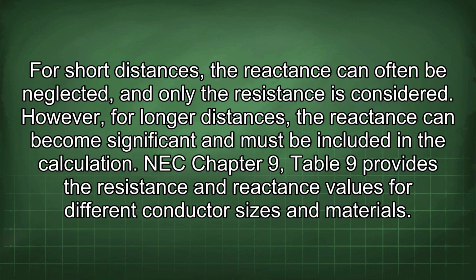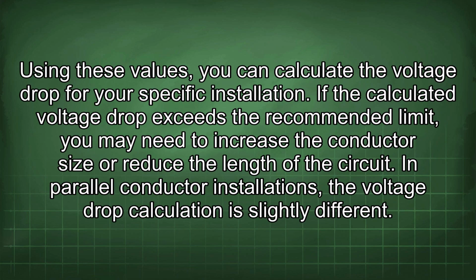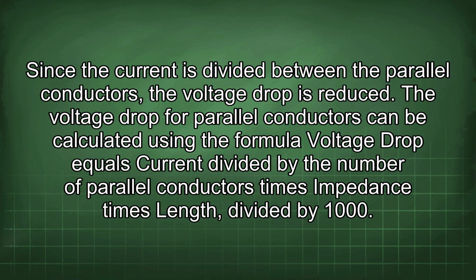NEC Chapter 9, Table 9 provides the resistance and reactance values for different conductor sizes and materials. Using these values, you can calculate the voltage drop for your specific installation. If the calculated voltage drop exceeds the recommended limit, you may need to increase the conductor size or reduce the length of the circuit. In parallel conductor installations, the voltage drop calculation is slightly different. Since the current is divided between the parallel conductors, the voltage drop is reduced.